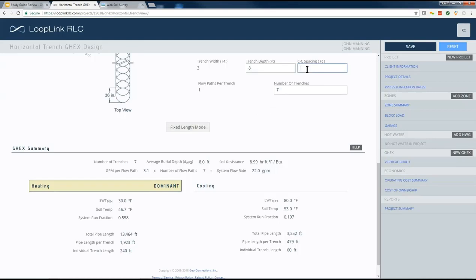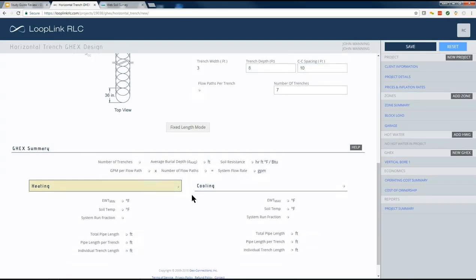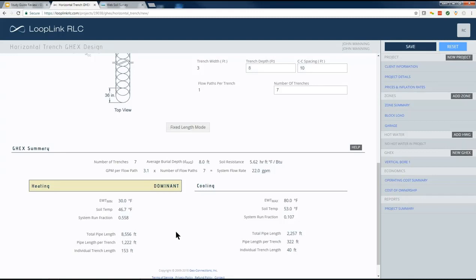The other thing that you can do is see the impact of spreading them out. So rather than touching each other on edge, let's spread them 10 feet on center. By doing that, you can see we drop our total pipe length down from whatever it was to 8,500 feet of pipe, 1,200 feet per trench, about 150-foot trench lengths.